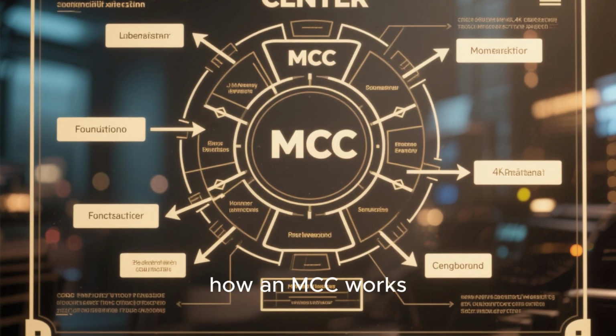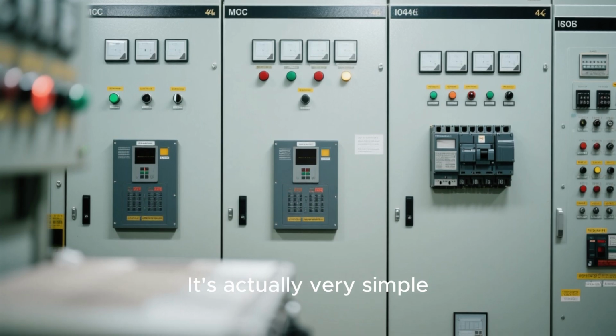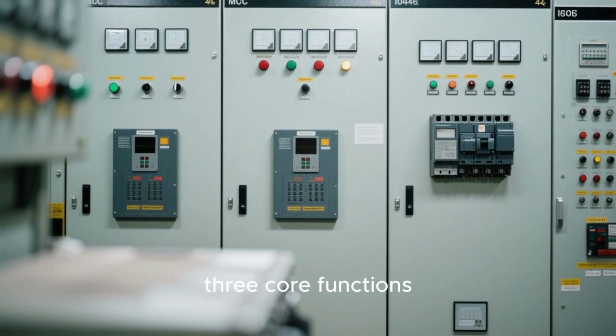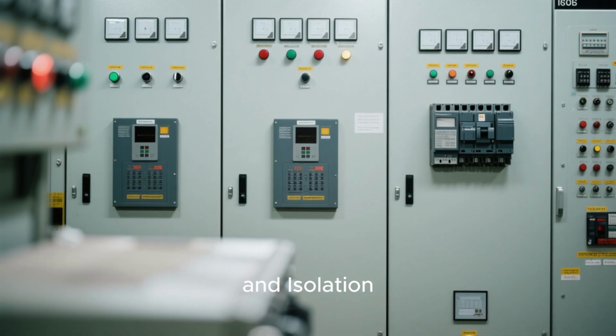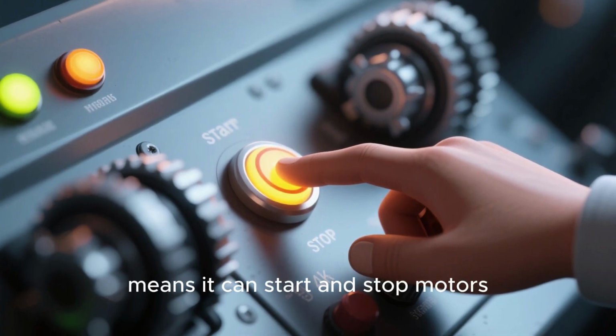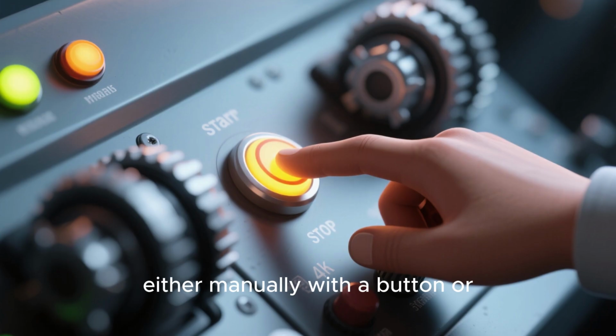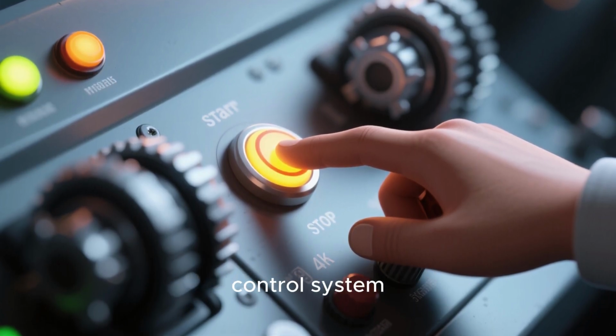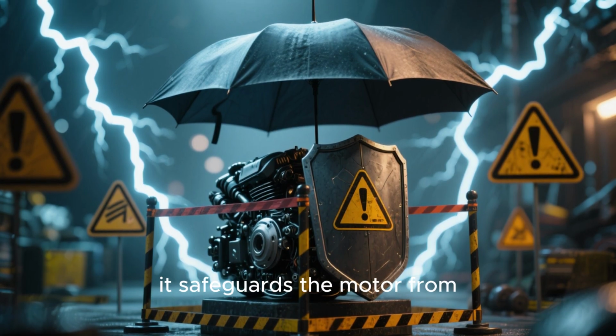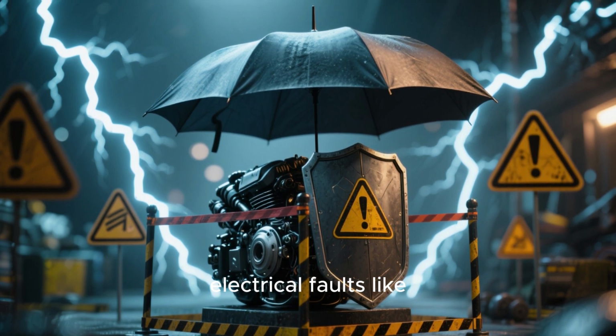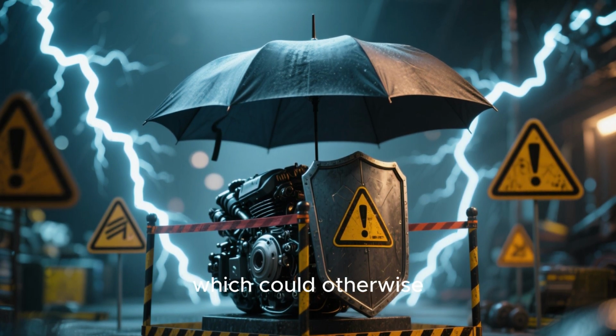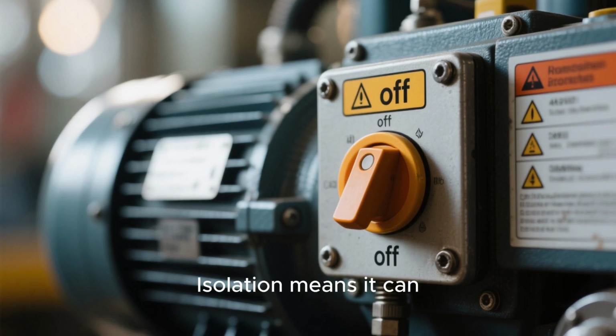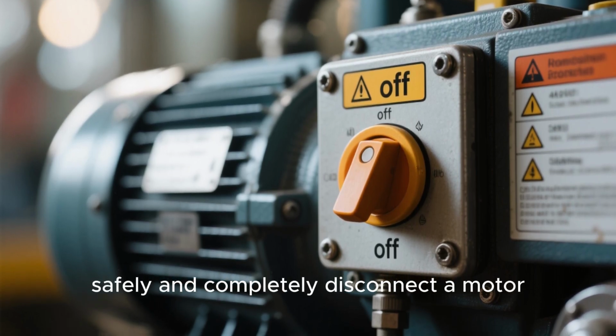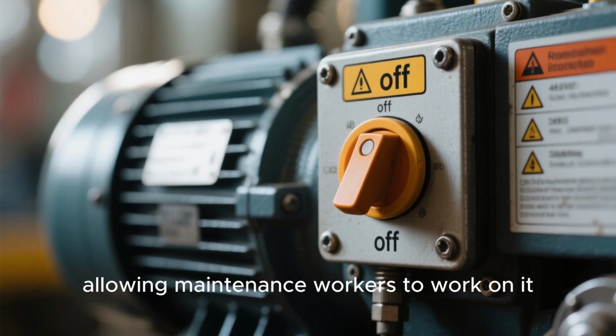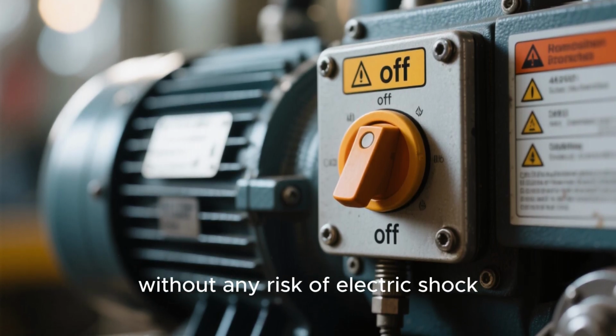Let's talk about the basic principle behind how an MCC works. It's actually very simple and boils down to three core functions: control, protection, and isolation. First, control means it can start and stop motors, either manually with a button or automatically through a control system. Second, protection means it safeguards the motor from electrical faults like overloads or short circuits, which could otherwise destroy the motor. And third, isolation means it can safely and completely disconnect a motor from the power supply, allowing maintenance workers to work on it without any risk of electric shock.